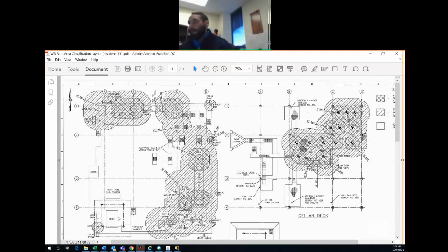And the zones would be designated similar to this hatch mark, except one might show a kind of design where it looks like polka dots that are spaced out, and then they would start with the hatching for the zone 1 and zone 2 areas. So, okay, in general, the difference between 500 and 505 is that 500 shows divisions and 505 shows zones.